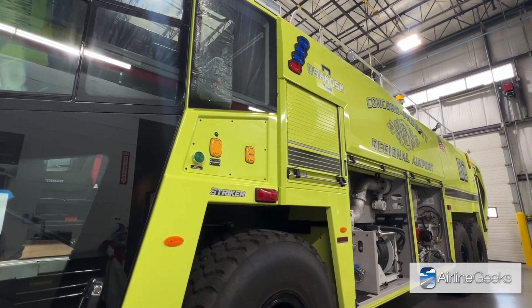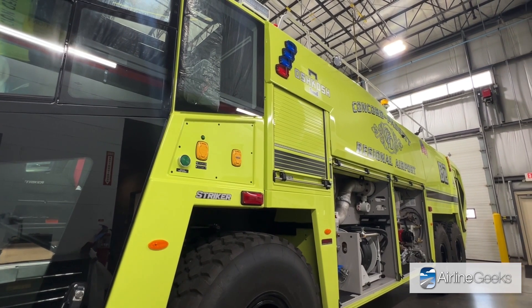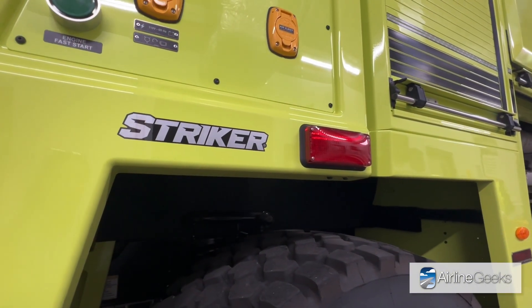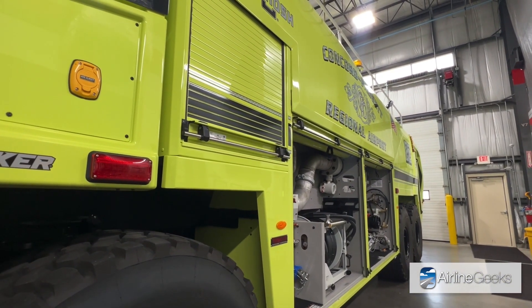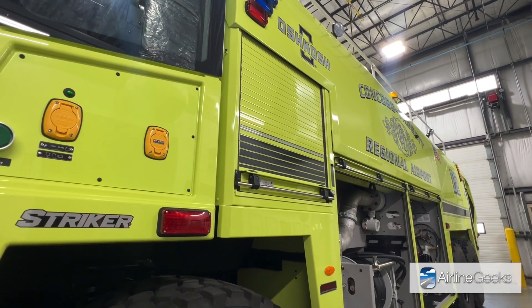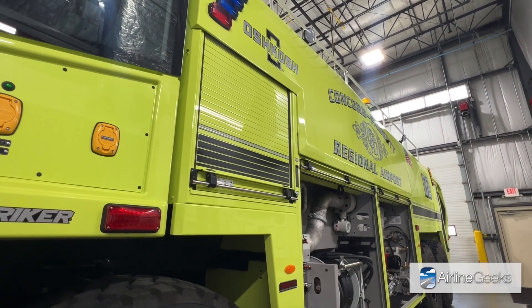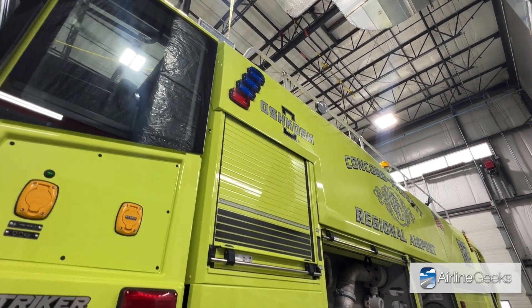We're looking at an Oshkosh Striker — this is a six-by-six Oshkosh Striker. We make the product in three models: a four-by-four, a six-by-six, and an eight-by-eight. Each variant carries a different amount of agent based on FAA requirements at different airports. This specific truck, going to Concord, North Carolina, has 3,000 gallons of water, about 300 gallons of foam, and 500 pounds of dry chemical powder.